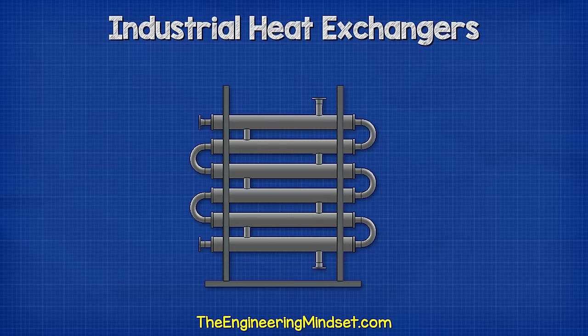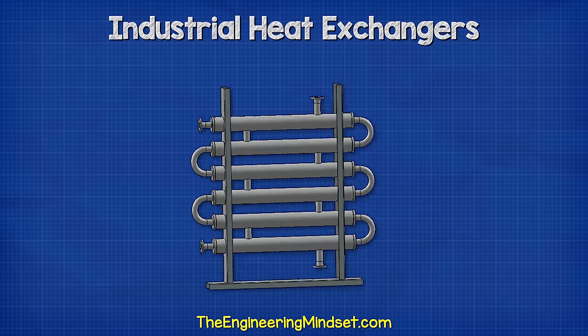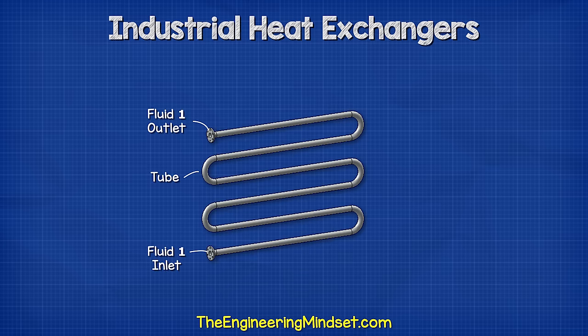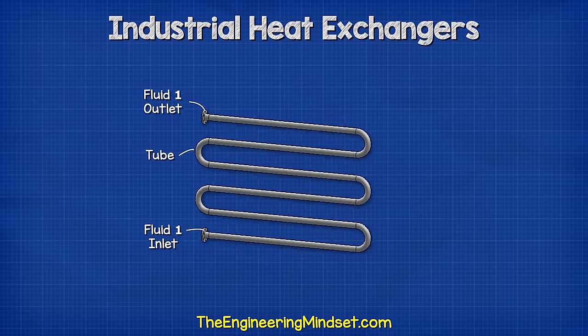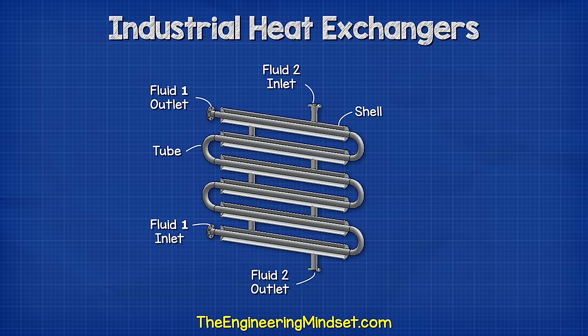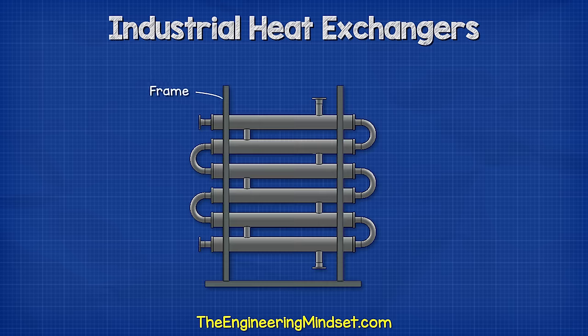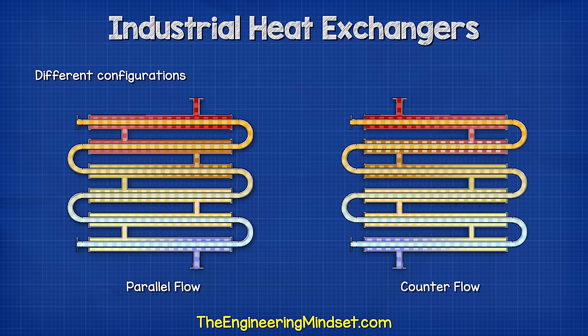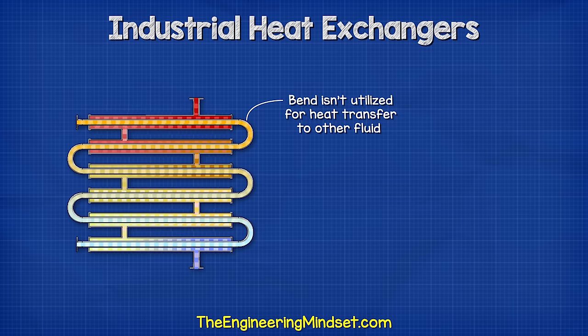Double pipe or tube-in-tube heat exchangers look something like this. Similar to the shell and tube design, we have a tube which runs back and forth between an inlet and an outlet, surrounded by a shell with another inlet and outlet. A metal frame holds the unit in place, and typically everything is made from stainless steel. One fluid flows through the tube and another through the shell, separated by the tube wall, transferring thermal energy through it. The different configurations result in different temperature profiles and heat transfer. In this design, the bend at each end isn't utilised for heat transfer, so some heat can be wasted there — however, manufacturing this heat exchanger is cheaper and easier.